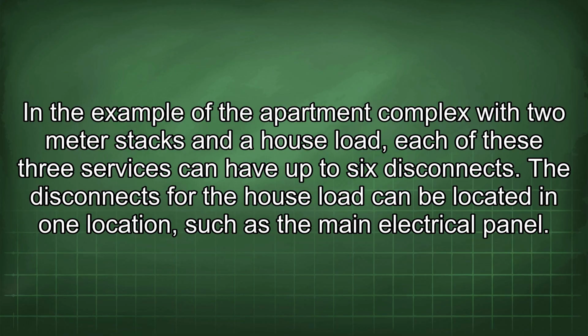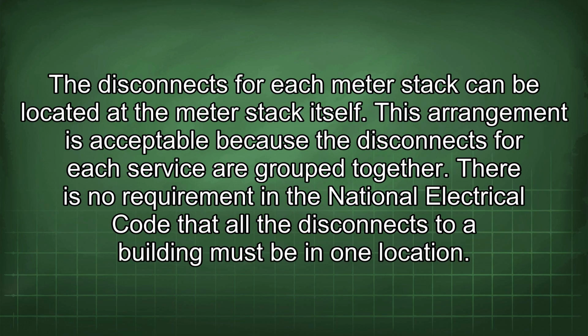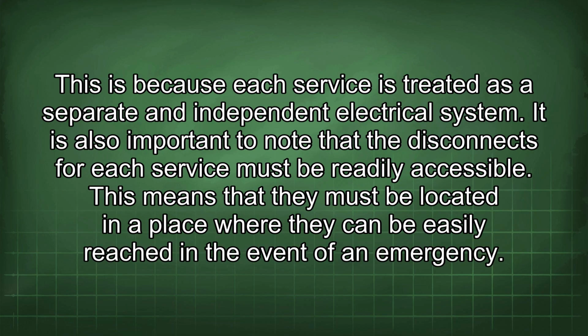The disconnects for the house load can be located in one location, such as the main electrical panel. The disconnects for each meter stack can be located at the meter stack itself. This arrangement is acceptable because the disconnects for each service are grouped together. There is no requirement in the National Electrical Code that all the disconnects to a building must be in one location. This is because each service is treated as a separate and independent electrical system.